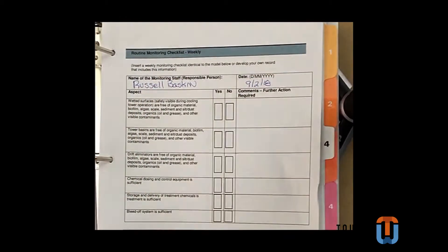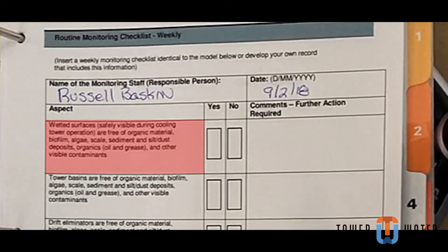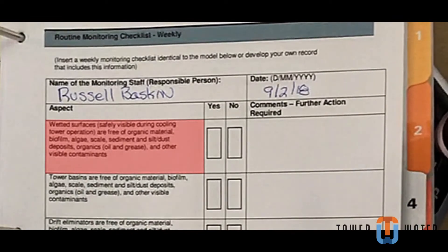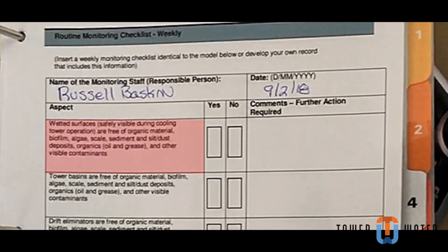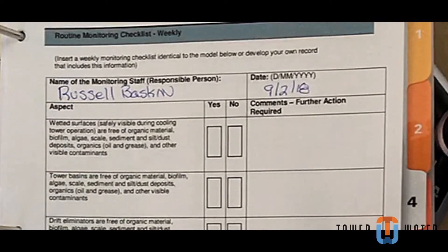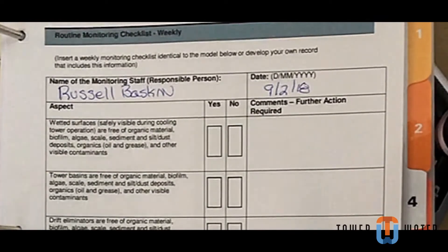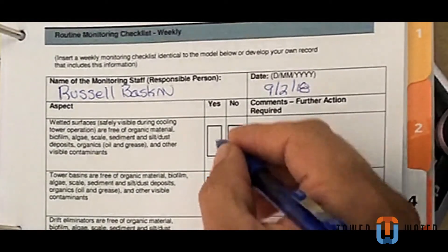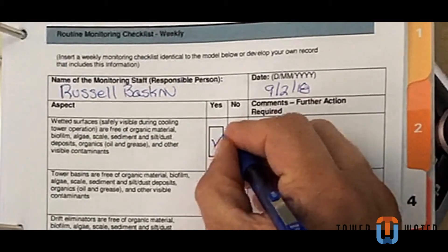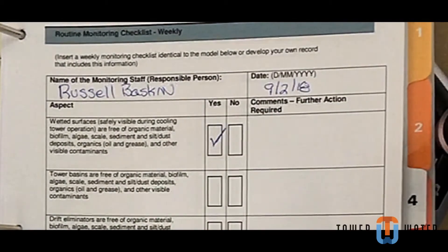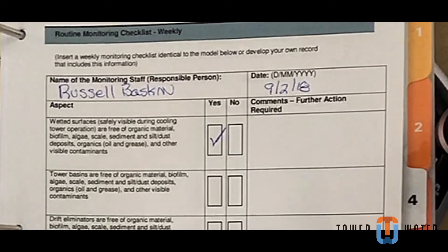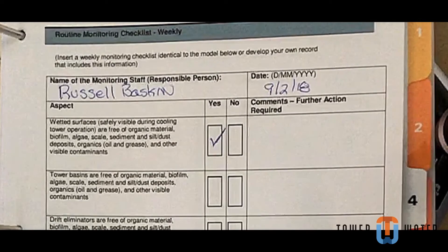Fill out your full name and date at the top of this page, and then begin answering each of the corresponding questions. Question 1: Wetted surfaces are free of organic material, biofilm, algae, scale, sediments, silt, dust deposits, organics such as oils and greases, and other visible contamination. Check yes if no or low amounts of contamination exist. Check no if contamination is visible. If you check no, in comments write where it exists, when and how it will be removed.